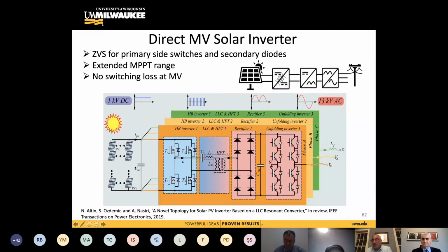You can use a resonant solid-state transformer to do this, and doing that you can directly go to medium voltage with several levels of optimization. This is the DC here; you put a DAB here. On the secondary, of course, this is a diode bridge—we did not need this to be bidirectional, so we put a diode bridge here. You put a resonance, a series-loaded resonant converter here with a capacitor in series, and then this voltage you take DC to pulse voltage here.